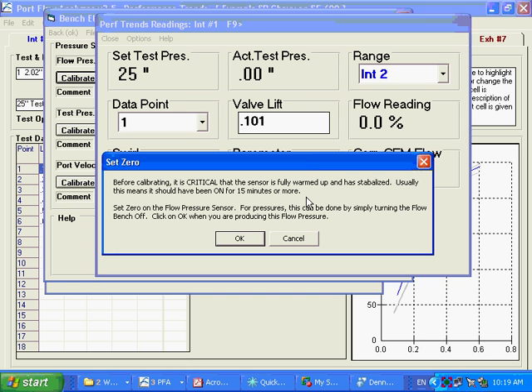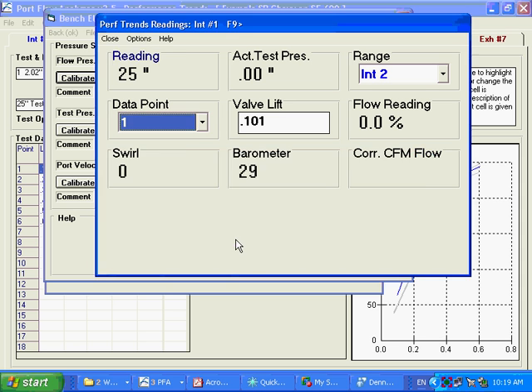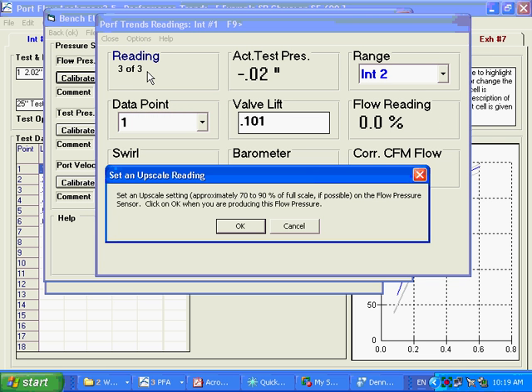Zero pressure is very easy to set. It just means that the flow bench is turned off. There's no flow going through it. So the sensor is seeing zero pressure. When it's producing zero pressure, you click on OK, and you can see up here it took 3 readings. And then it says produce an upscale reading, 70-90% of full scale if possible. And because we're on a Superflow 600 with an incline manometer, it actually reads in percent full scale, 0 to 100%. That means set about 80-85% on the incline manometer.